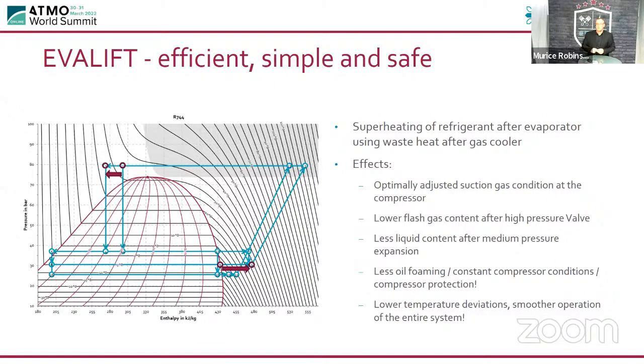So constant compressor conditions, your compressors are protected, and low temperature deviations and a much smoother operation of the entire system. Because we're controlling the superheat of the system, we can actually make sure that we don't have large deviations in suction temperatures and discharge temperatures and so on. So it really, really works well.